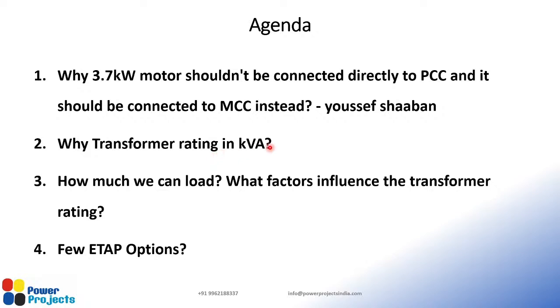A transformer is rated in kVA because a transformer doesn't have independent real and reactive power constraints. How much we can load purely depends upon many factors. That's what we put as a question. It depends on the grid voltage, the transformer impedance, the transformer X by R ratio, and the load power factor, right? And these are all external factors. With respect to the internal factors, these are probably non-electrical parameters, like ambient temperature, wind velocity, and previous loadings, etc.